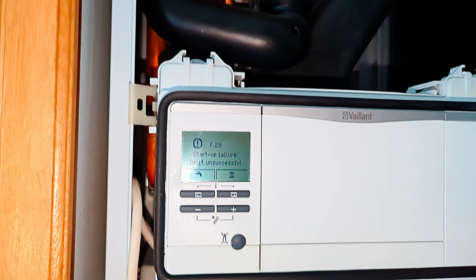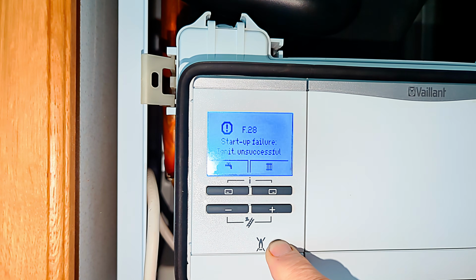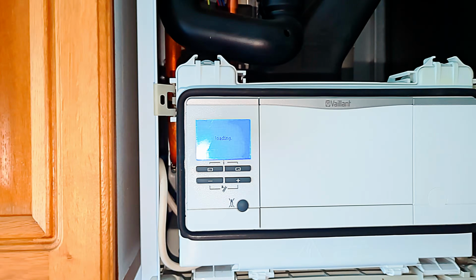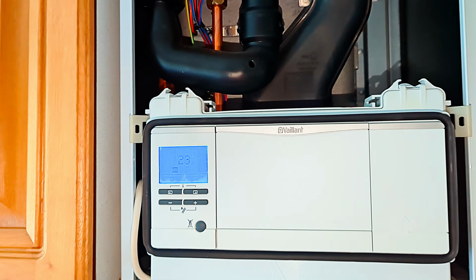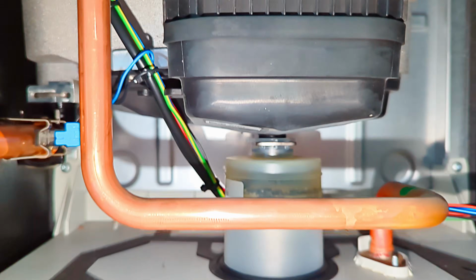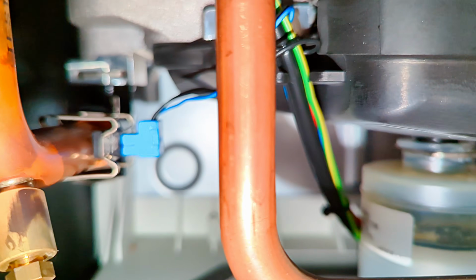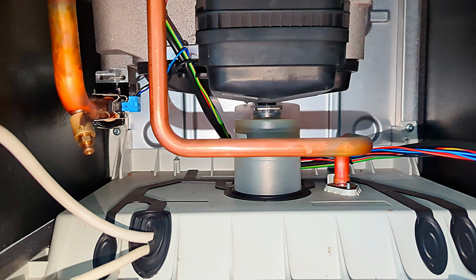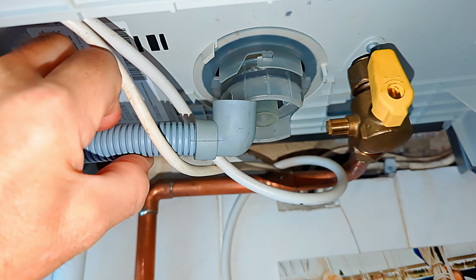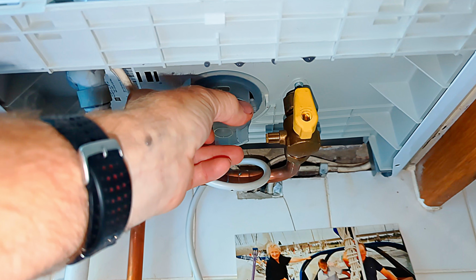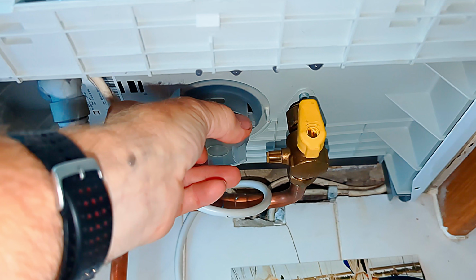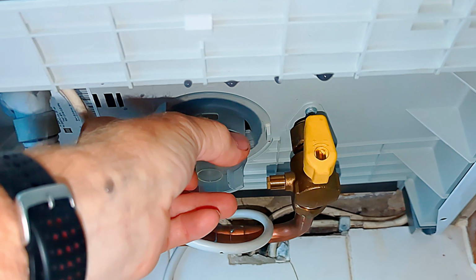Once again, a little word of caution. Now, I was called to this boiler because it had stopped operating. I took the cover off to see what the problem was and obviously very quickly realised that the condensing trap was blocked up. I then cleared the blockage and the boiler started working straight away. I then thought this would be a really useful video because, like I said, this is not the first time I've come across this particular boiler with a blocked condensing trap. So I went through the whole process again and obviously filmed myself doing it. So the word of caution is when I initially unblocked it, a lot of water poured out the bottom of the boiler and it kind of sprayed all over the place. And you can see lots of drips here on the front of the boiler where I'd already cleared it out. So do be careful when that water comes gushing out.